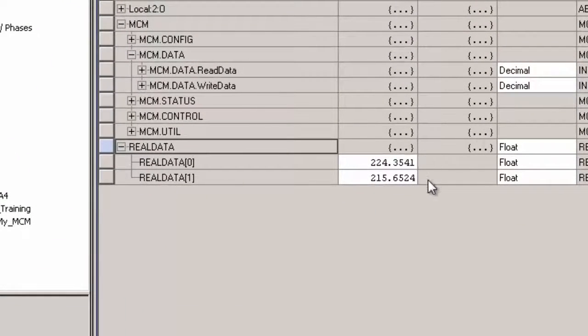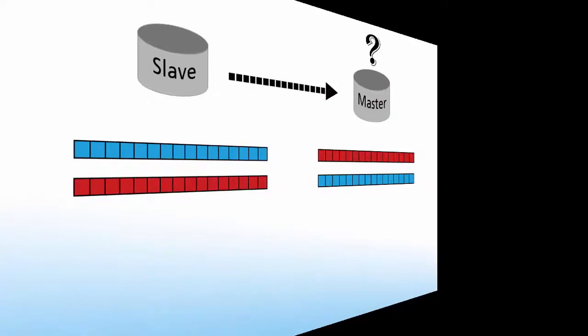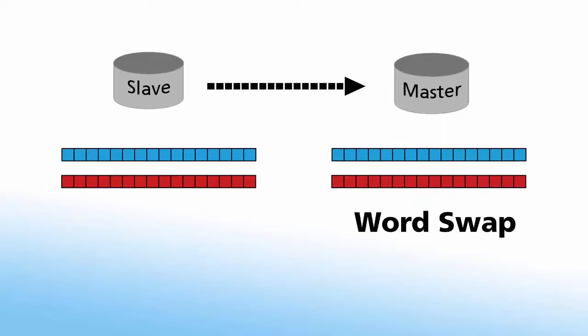If you're using Modbus and you get to this point and your data does not look right, it may be because the two 16-bit registers were not recombined in the correct order. Different industrial vendors order them differently. In this case you would simply swap the word order to correct them.